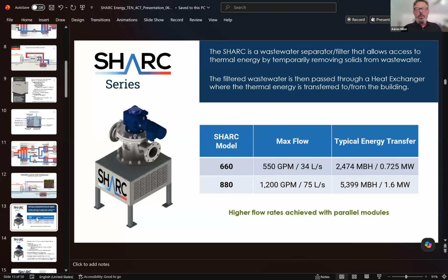Sure. Okay. Whereas the Piranha really is a one-way street, waste heat in, potable hot water out, the SHARC is our larger system, our namesake, a passive filtration system. The easiest way to think about this is geothermal, but instead of using groundwater, we're using alternative water sources. Black water, the nasties of the nasties, gray water, data center chilling. It doesn't matter. As long as you've got a water stream, even with solids in it, that we can run through our system and properly filter out enough of those solids, we can use that wastewater stream as a heating source or a heating sink.